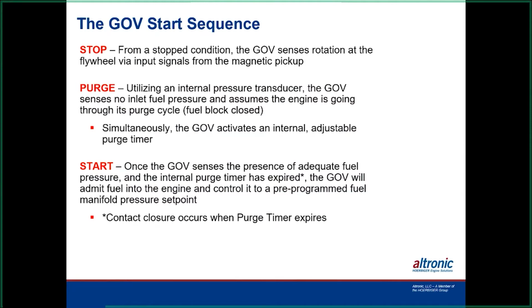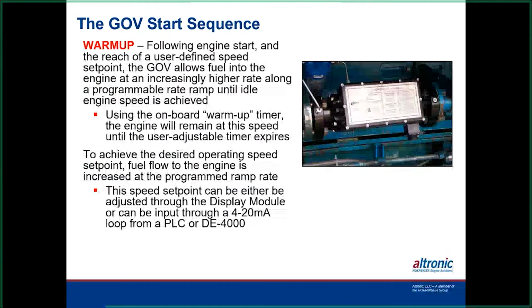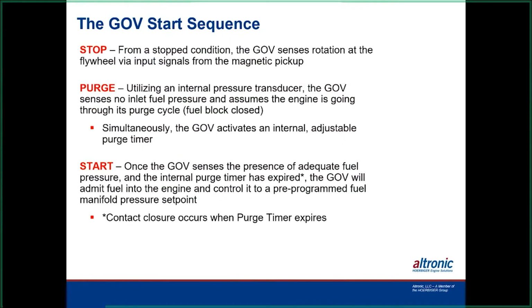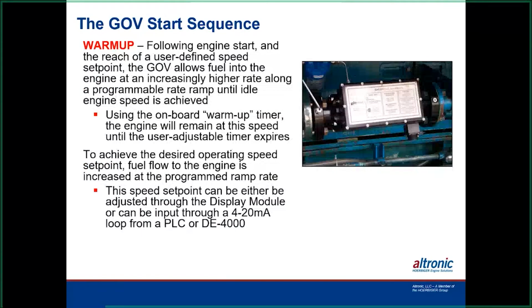And then when the timer is timed out, after the purge timer is out, it will go into the start mode, where we're triggered to open up the block and bleed valve to allow gas to come in to the valve, and then it's controlled by a pre-programmed fuel manifold pressure. And then we have a warm-up timer on it. Again, if the engine has already been warmed up, it can be triggered internally to shut off, or you can do it from the keypad. Then it will go right into the run mode on it.